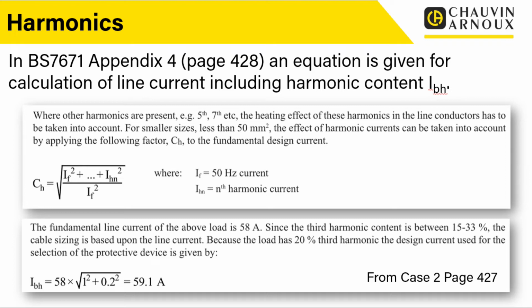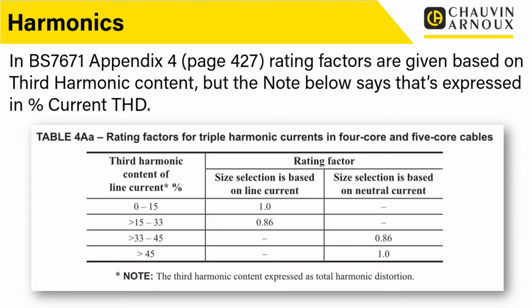Now you'll notice there is a bit of strange use of language here. The language is very confusing between third harmonic content and THD. They seem to use the phrases interchangeably, and obviously if we were looking at just third harmonic content, that would be a different value to THD. But if we have a look at the next slide, there is a little note underneath. So in Appendix 4, rating factors are given based on third harmonic content. But the note below says that's expressed in percentage current THD. So the third harmonic content is expressed as total harmonic distortion.